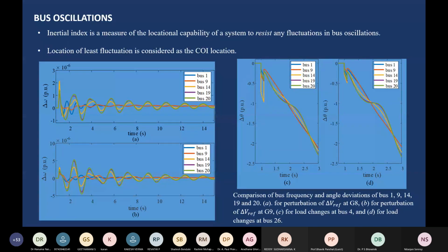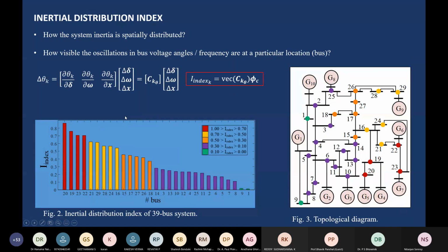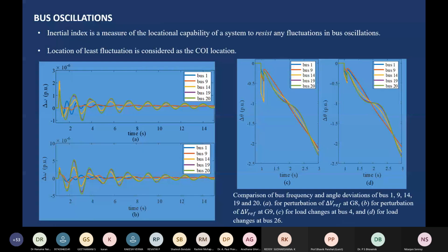Sorry about that. So this kind of oscillations, which are obtained from oscillation analysis of the linearized model, can be verified very easily using nonlinear models, as shown here. The nonlinear model here confirms that bus number 1 and bus number 9 oscillations are very low, while bus number 19 and bus number 20 oscillations are very high. So bus number 19 and bus number 20 are very, very vulnerable buses. Bus number 9 and bus number 1 are the center of inertia of the system.